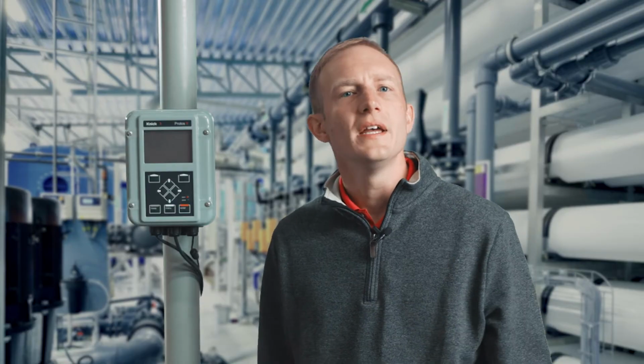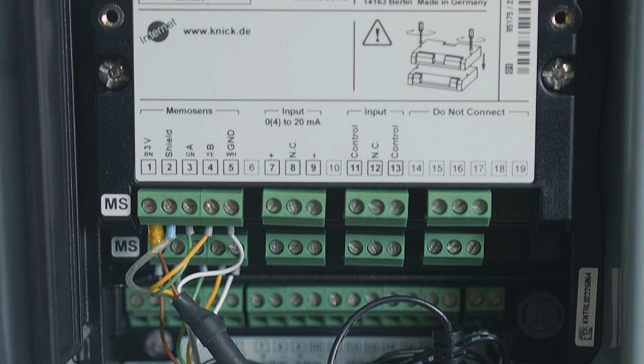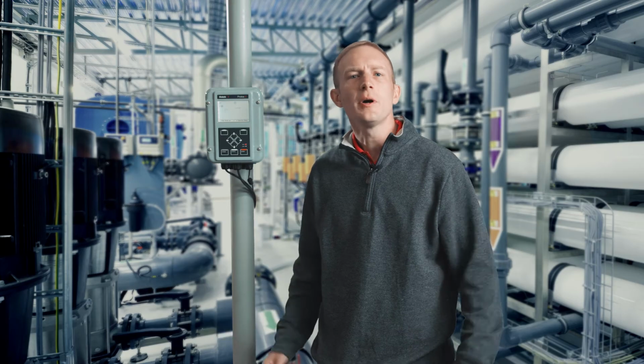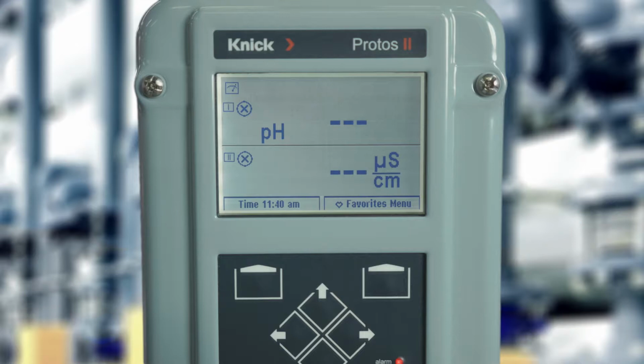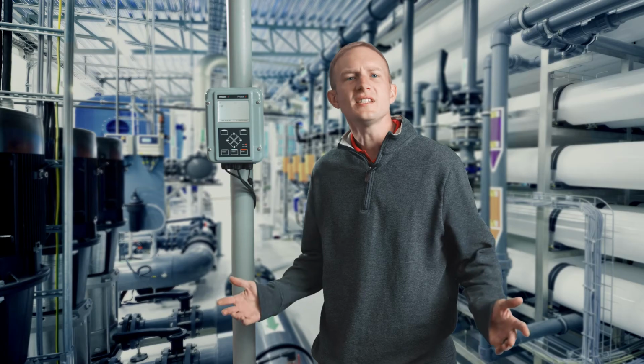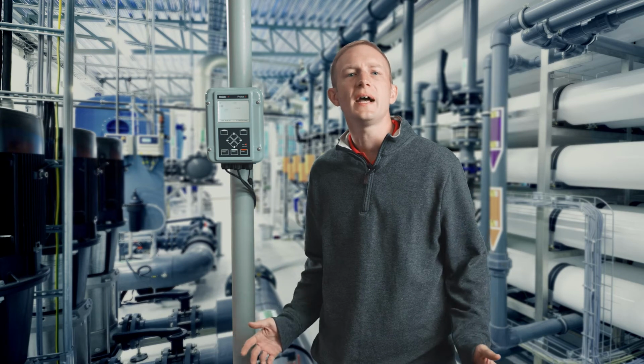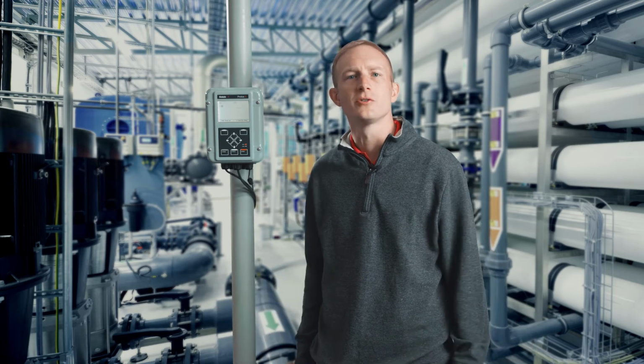Before you begin, ensure your power supply, sensor cables, and any outputs you are utilizing are connected to the terminal blocks on the transmitter base and input modules. After applying power, you'll notice that we currently have an error icon flashing on top of the main screen. This is indicating that no sensor is connected on both channel 1 and channel 2.